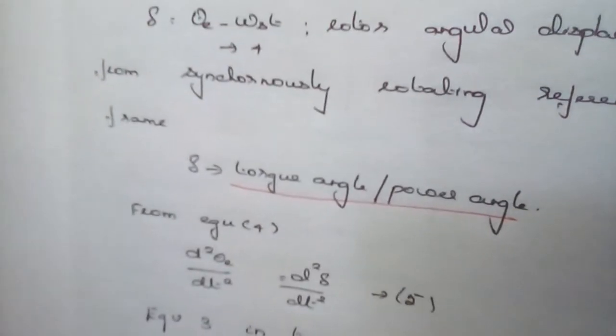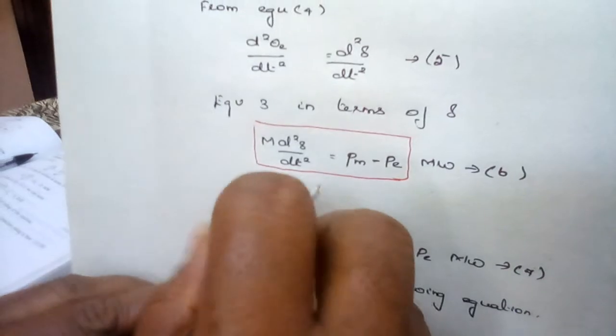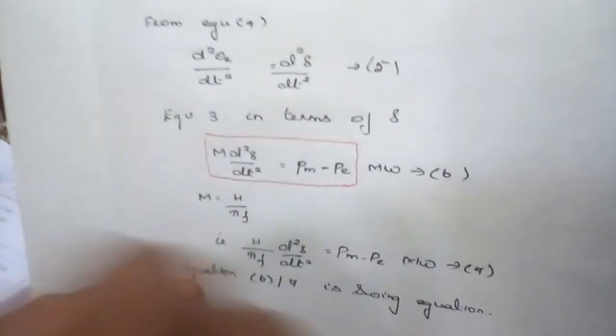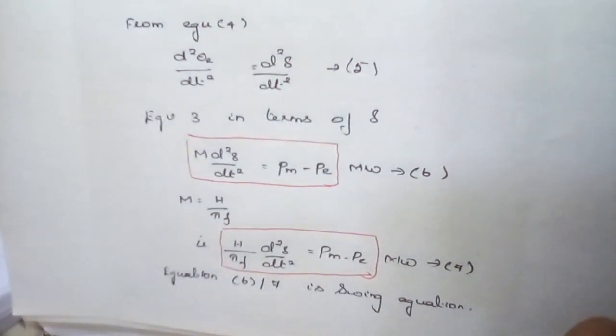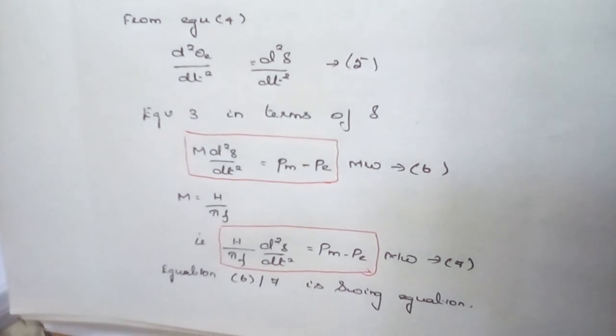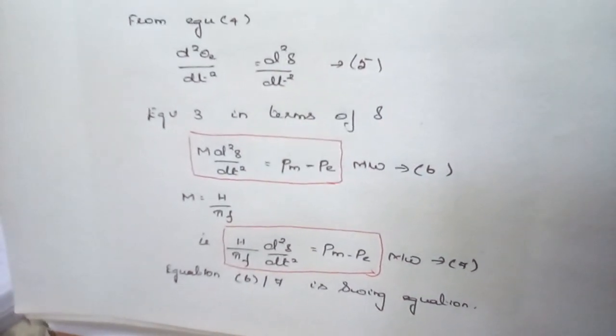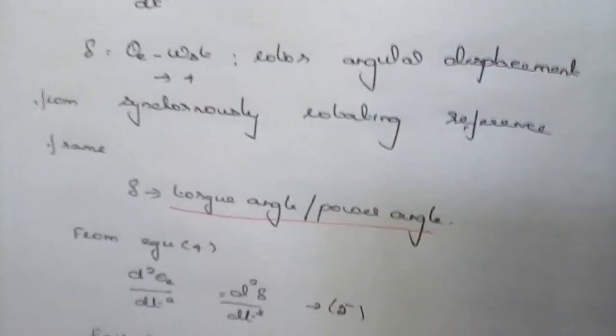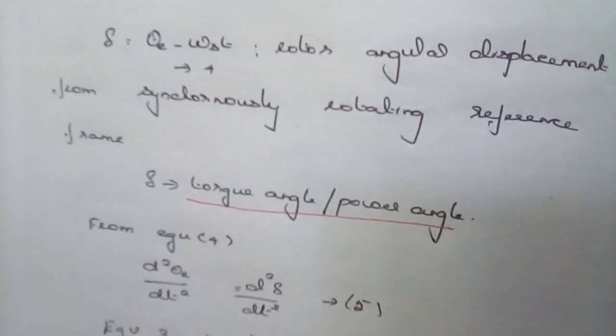Delta is known as the torque angle or power angle. The swing equation can be written as: M · d²δ/dt² = Pm − Pe, or equivalently as H/πf · d²δ/dt² = Pm − Pe. These two forms are the swing equation and they describe the rotor dynamics of the synchronous machine, either in generating or in motoring mode. The obtained expression is a second-order differential equation where the damping term is absent, based on the assumption of a lossless machine, and the damper winding torque is also ignored.